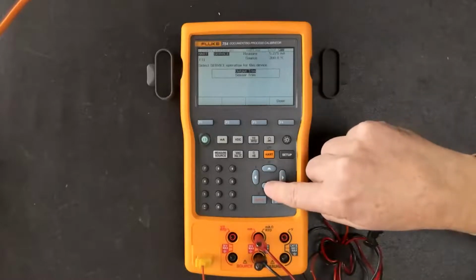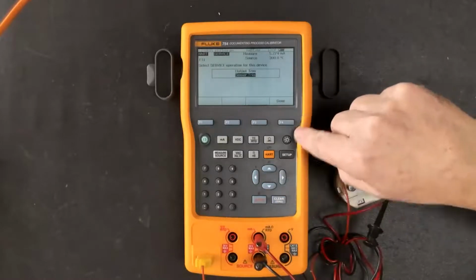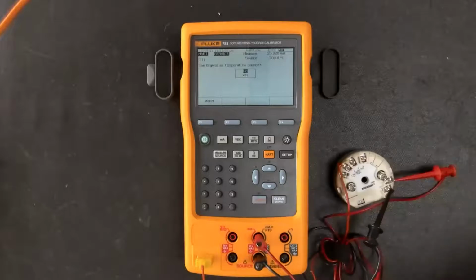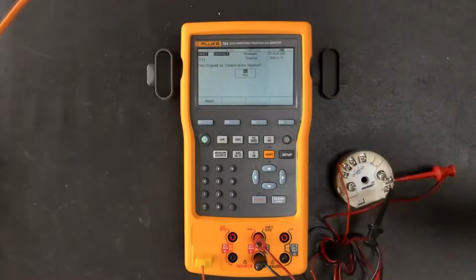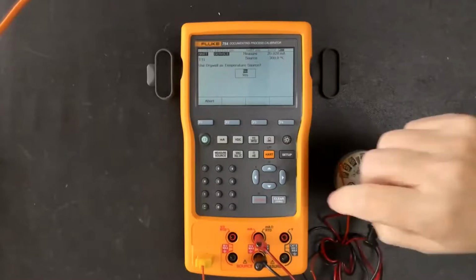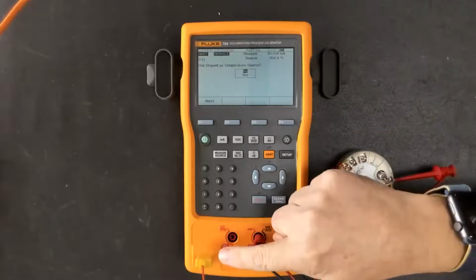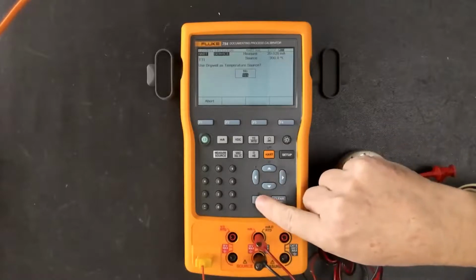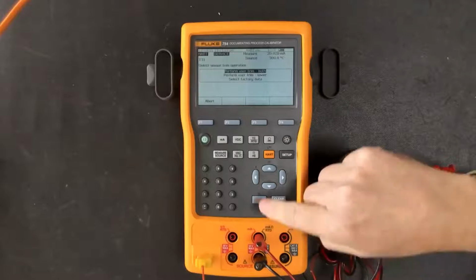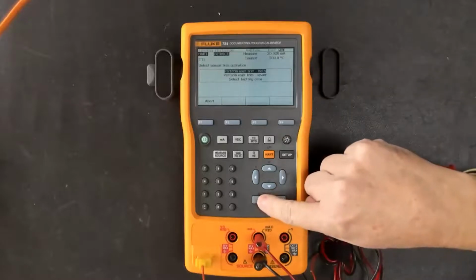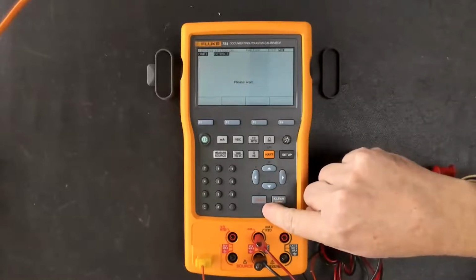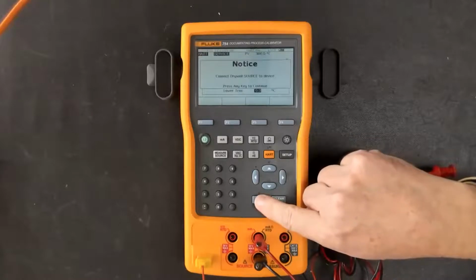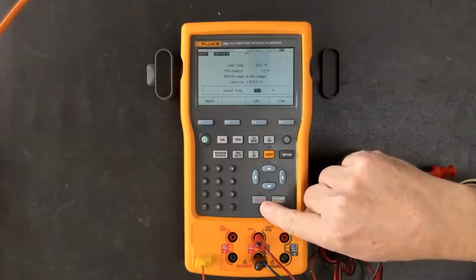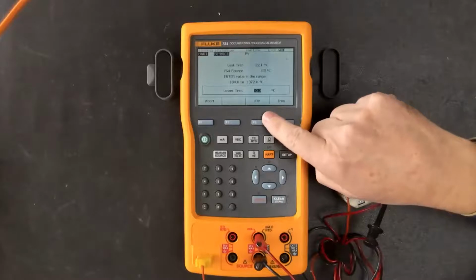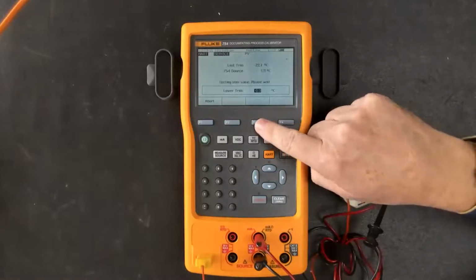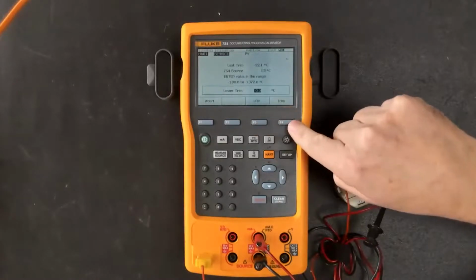Next, we can do the sensor trim, and we'll enter here. If we have a dry well in the setup, we could use that, but we don't. We're just using the output of the 754, so we'll go ahead and do that. We're going to do both the upper and lower values. Okay, next source. Okay, lower range value is 0, so we're going to set that in trim.